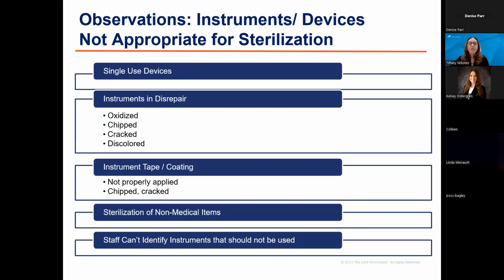Instruments and devices not appropriate for sterilization, right? There should be an inspection period in sterile processing where the people in pack and prep or even in decontamination are looking to see if these instruments need to be removed from service, right? Single-use devices: I'm convinced nobody intends to reprocess single-use devices because it's not allowable by the FDA unless you're a third-party reprocessor, but sometimes they accidentally find their way in there. Instruments in disrepair, so they're oxidized, chipped, cracked, right? That means there's a possibility, one, that they aren't able to be appropriately sterilized, but two, they could be a safety issue for patients.